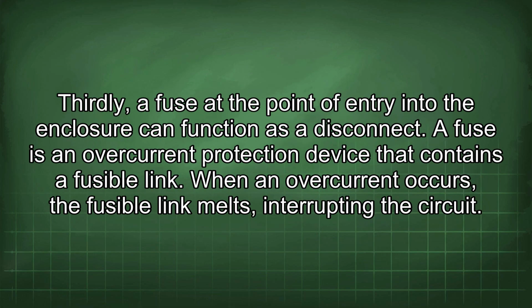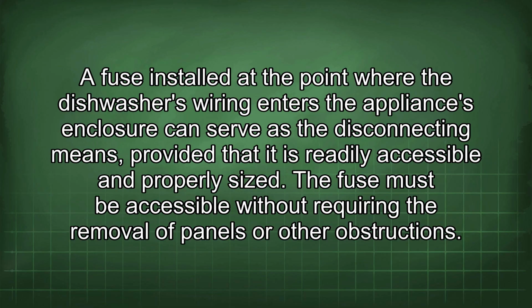Thirdly, a fuse at the point of entry into the enclosure can function as a disconnect. A fuse is an overcurrent protection device that contains a fusible link. When an overcurrent occurs, the fusible link melts, interrupting the circuit. A fuse installed at the point where the dishwasher's wiring enters the appliance's enclosure can serve as the disconnecting means, provided that it is readily accessible and properly sized. The fuse must be accessible without requiring the removal of panels or other obstructions.